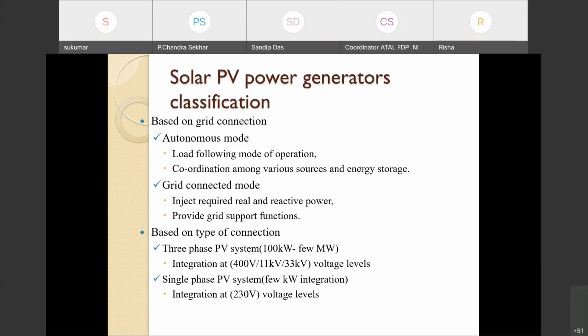And since the load is a variable one, as well as the source is a variable one in case of a solar system, the energy storage is a requirement for an autonomous mode. On the other hand, for the grid connected mode of operation, since the voltage of the grid is fixed, we cannot do anything with the voltage. Then we can only inject current. So that current injection is there. So we can inject real and reactive power to the grid because voltage into current will become the power.